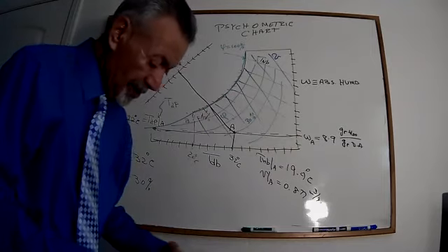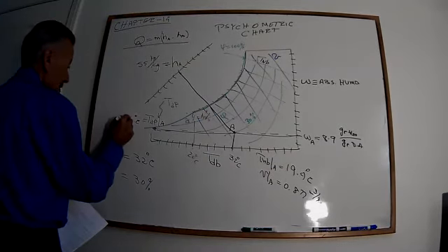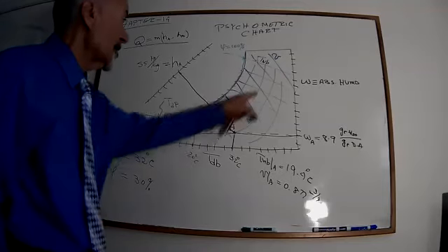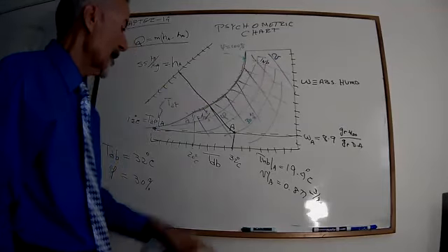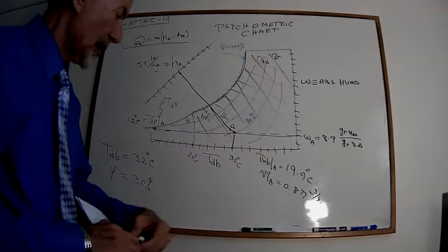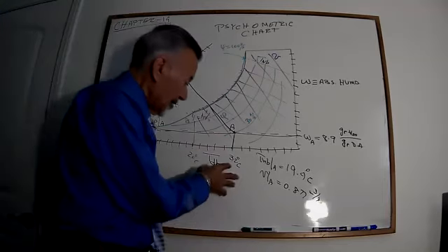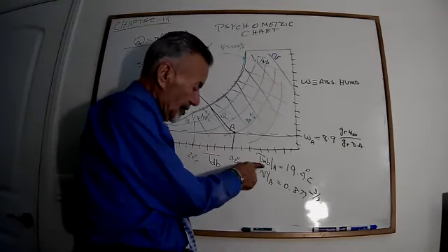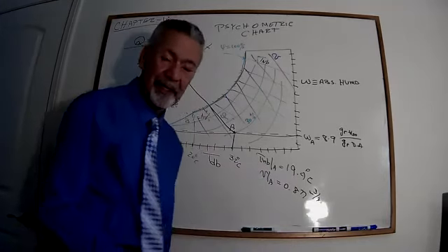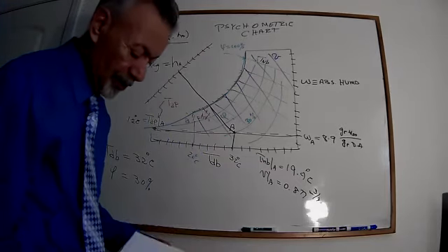Oh, I'm sorry, I made a mistake. This is not 22, that's 12. The dew point temperature is less than the wet bulb temperature and definitely much less than this temperature. So as you can see, we have the 32 degrees. What is our design point that we like to be? 19.9, almost 20 degrees Celsius. So that's what we like to see. That's what we like to do.